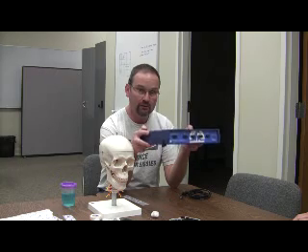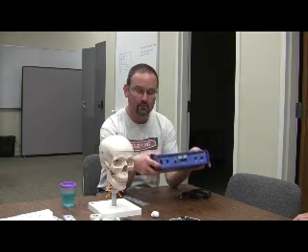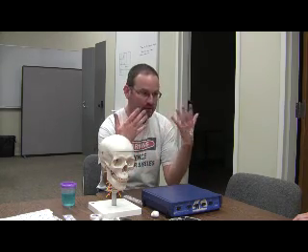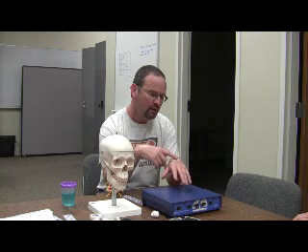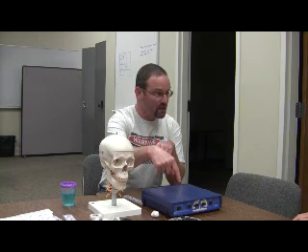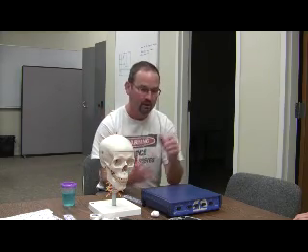What most people don't understand when they first encounter electrophysiological equipment is they think this box is supplying the power to the subject's body. In fact, it's exactly the opposite. Although this box does have a power supply, it's a supply to run the amplifiers. The bits that connect to the subject are completely passive. Electrons are constantly finding their way to the surface of your skin and moving laterally. By putting electrodes on the surface of your skin, those electrons can leave and go down a wire into the amplifier, where the amount of electron flow is measured, and then back out another wire onto your body at another spot. It's all done on the basis of a circuit.